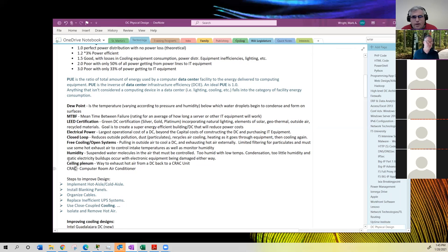The only thing I could add is the wiring in the plenum has to be plenum rated. That's actually a fire code rating. So usually the wiring that's plenum rated is just more expensive. It's definitely something you have to plan for.